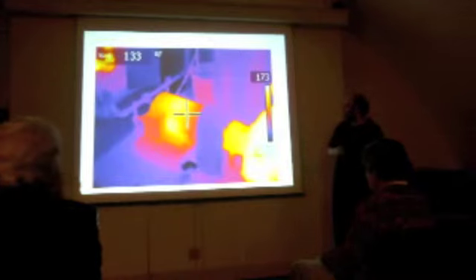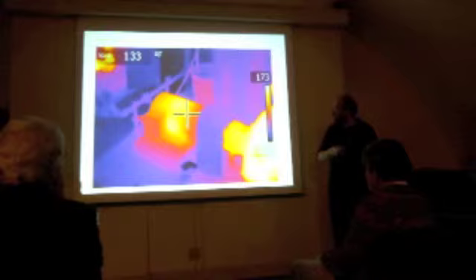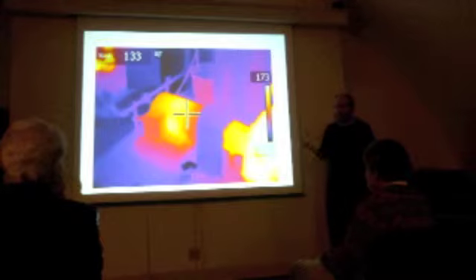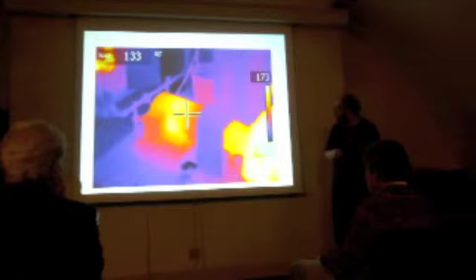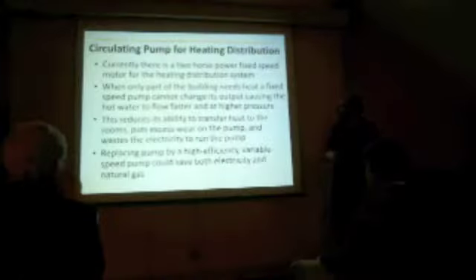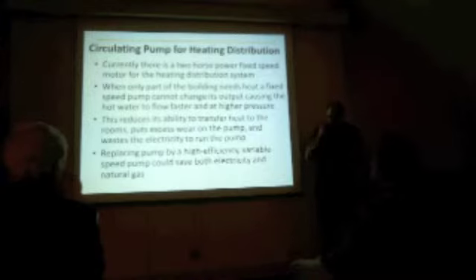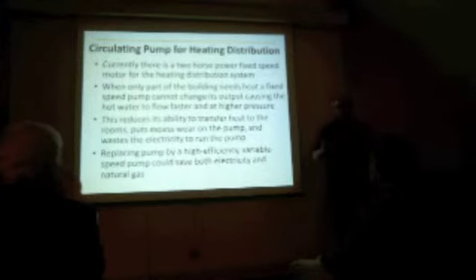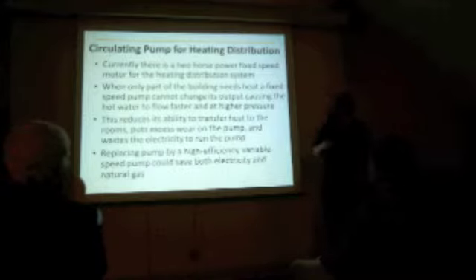And you can see here it is running now. You can see that the motor is electrically heating itself to about 133 degrees. And so running these motors at full speed all the time, whenever they click on, actually puts quite a bit of wear on these motors. And so there's a big savings that you can make by looking at switching away from the constant speed motor to what are called variable speed pumps.